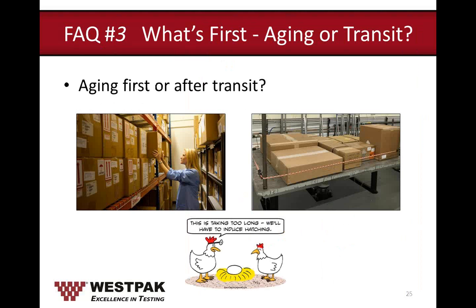Another common question: aging first or transit first? It sounds like the chicken-and-egg question. I suggest reviewing how you build and ship your devices. If you build to order — an order comes in, you build, then ship — I recommend transit first, then aging, because once the device reaches the customer, it will remain on their shelf for a while. But if you build consistently and ship when demand arises, then aging should be conducted first. As long as you test to your normal distribution environment and have data to support it, you should be okay.